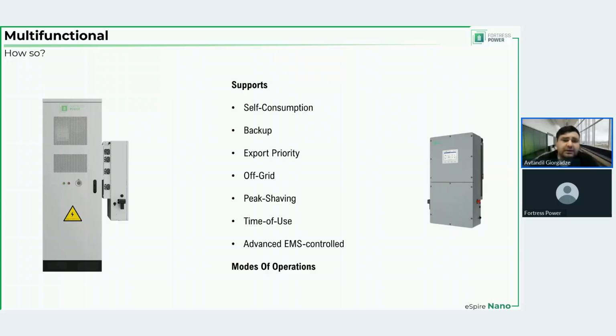Peak shaving, so it has threshold-based peak shaving. So you can select a power set point, and if the load demand, doesn't matter, may that be downstream of the inverter or upstream of the inverter, is higher than the threshold you've entered, the system will start discharging according to the limits that you set to it. And if the threshold is higher than the load demand, then the inverter can charge from the grid or can charge from the PV. Also, obviously, it will be using PV power when the threshold is exceeded by the load demand.